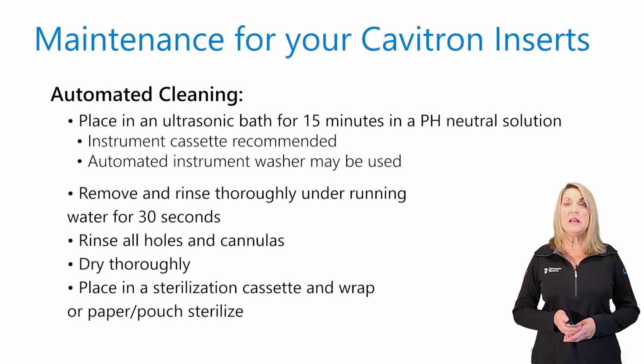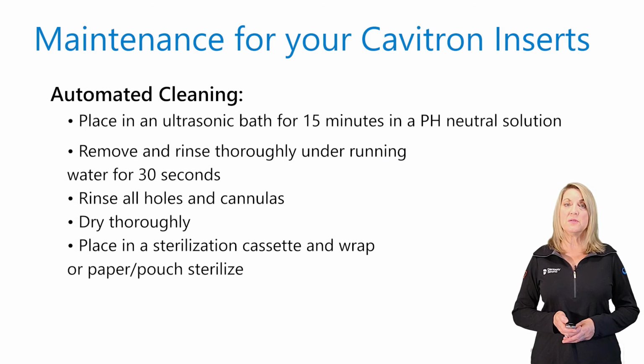Once you have finished cleaning the inserts, you need to rinse the inserts under running water for 30 seconds. Dry the inserts using a disposable lint cloth, and if using an instrument washer, follow the directions for use. Then place the dried inserts into a sterilization pouch or cassette and steam sterilize as manufacturer instructed.